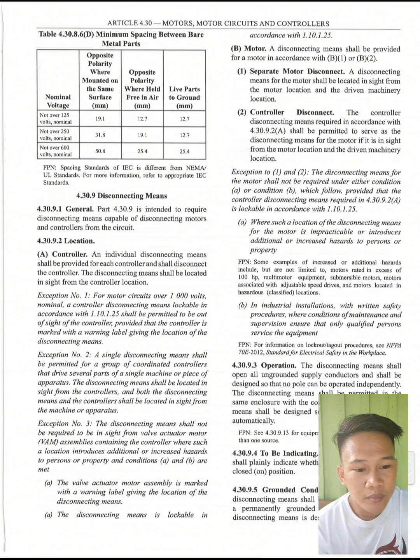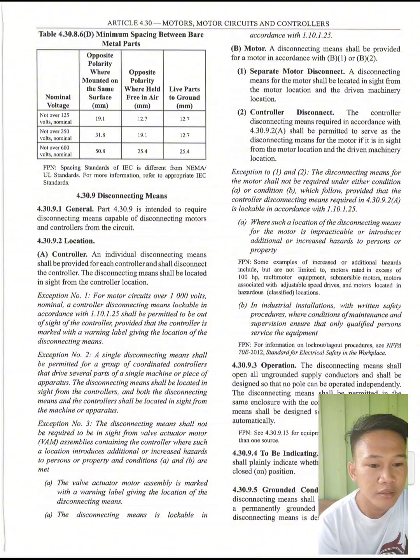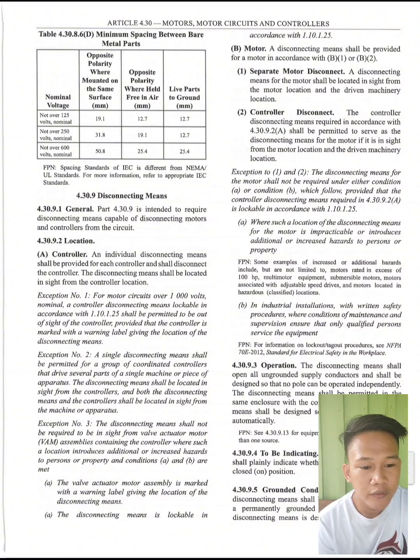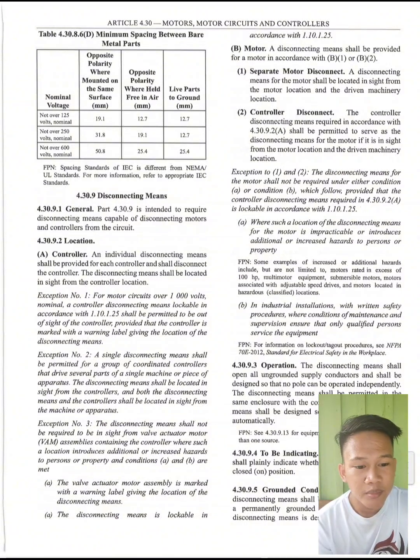So next, the motor. A disconnecting means shall be provided for a motor in accordance with B1 or B2. Separate motor disconnect: a disconnecting means for the motor shall be located in sight from the motor location and the driven machinery location. First, we have controller disconnect. The controller disconnecting means required in accordance with 4.30.9.2a shall be permitted to serve as the disconnecting means for the motor if it is in sight from the motor location and the driven machinery location.